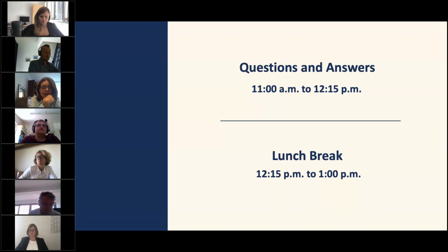And so going back to my comments about the rare disease program, if you have a rare disease and your confidence intervals are quite wide, there's no way you can confidently say this can be used for diagnosis. It can be used as an aid for diagnosis with other information, but it must be used in this context. So I think this is where the level of clinical evidence is important to consider when you define your intended use statement. And if you don't have the level of evidence to make a claim for diagnosis, don't make the claim. Think about what else you can use it for.